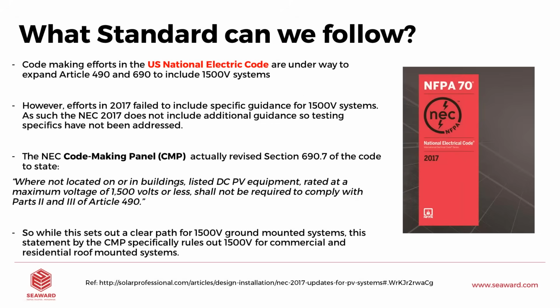So what standards can we follow with regard to 1500 volt systems? Well, right now, the answer is none, really. There are no standards we can turn to for 1500 volt systems. So we have to adapt what we already have. So here in the USA, we obviously have the NEC, the National Electric Code, and we have Article 490 and 690. And they are making efforts on the code making panel to include 1500 volt systems.